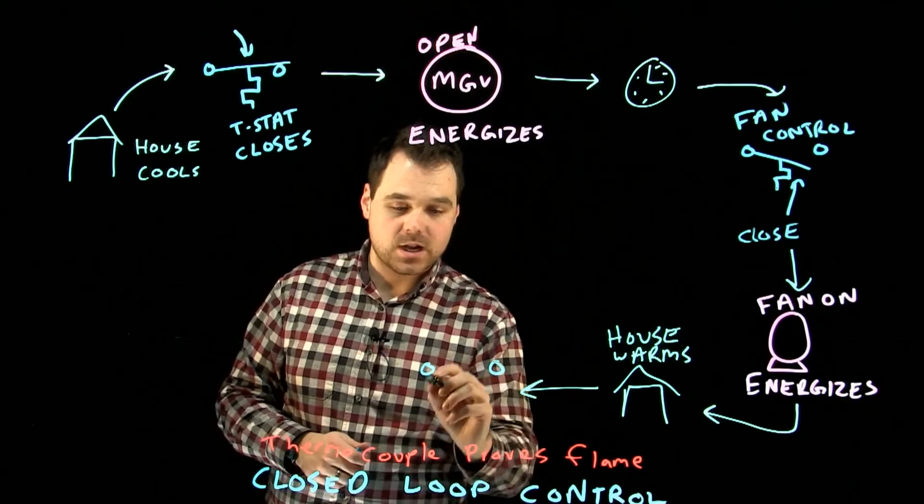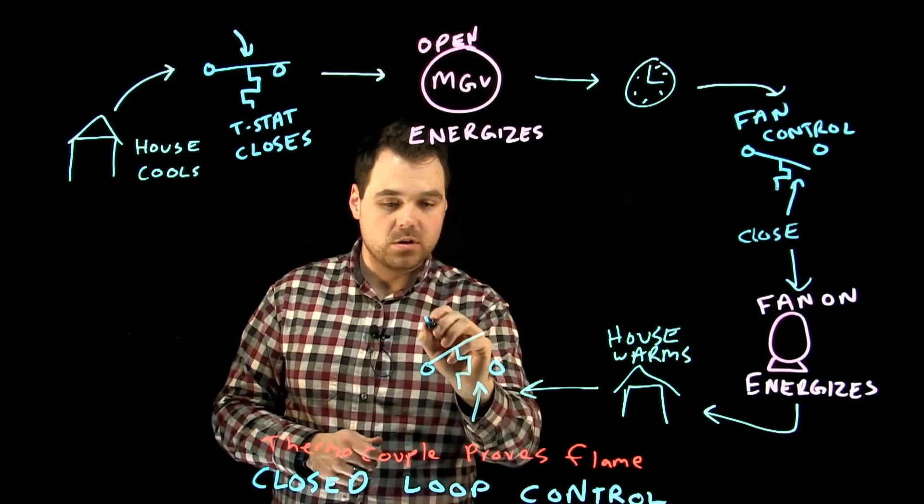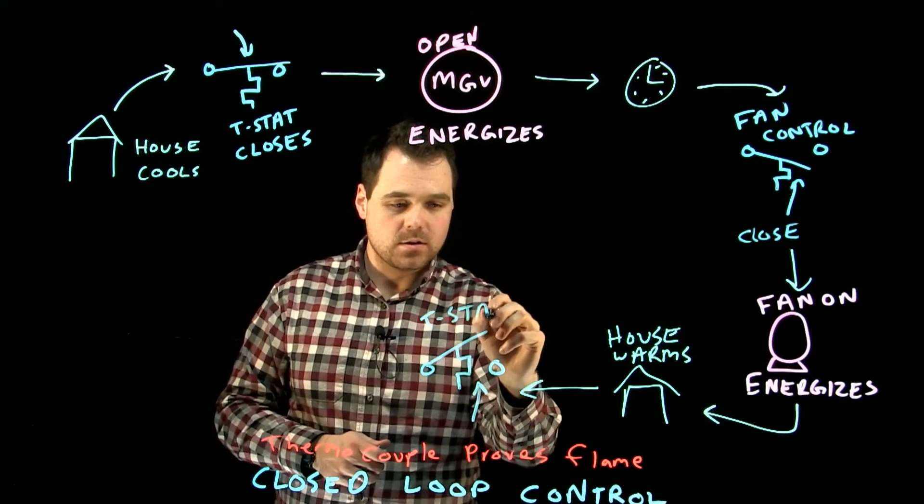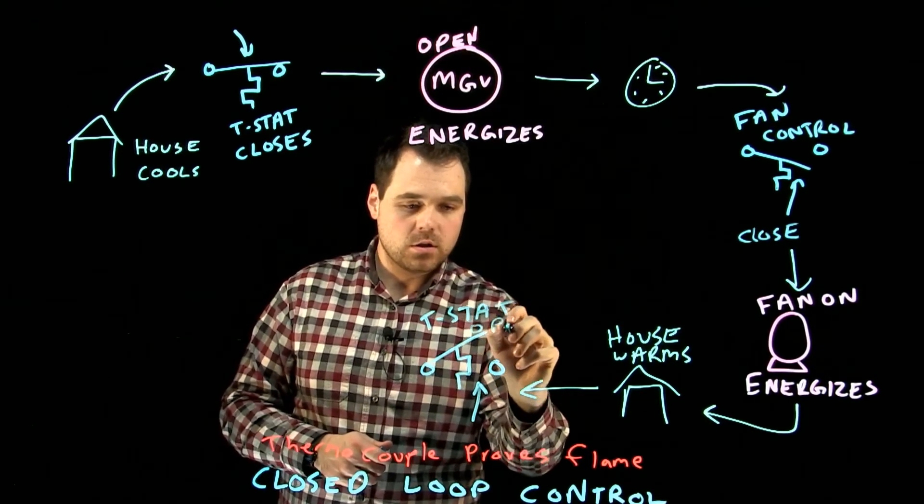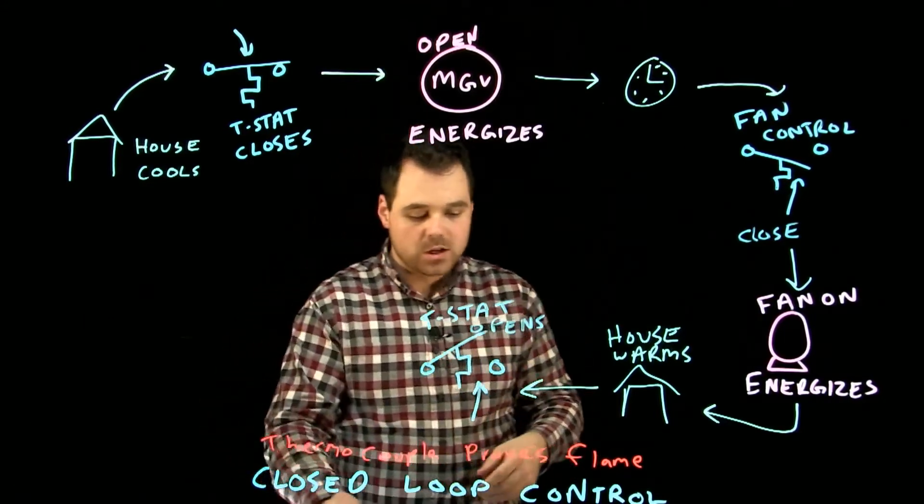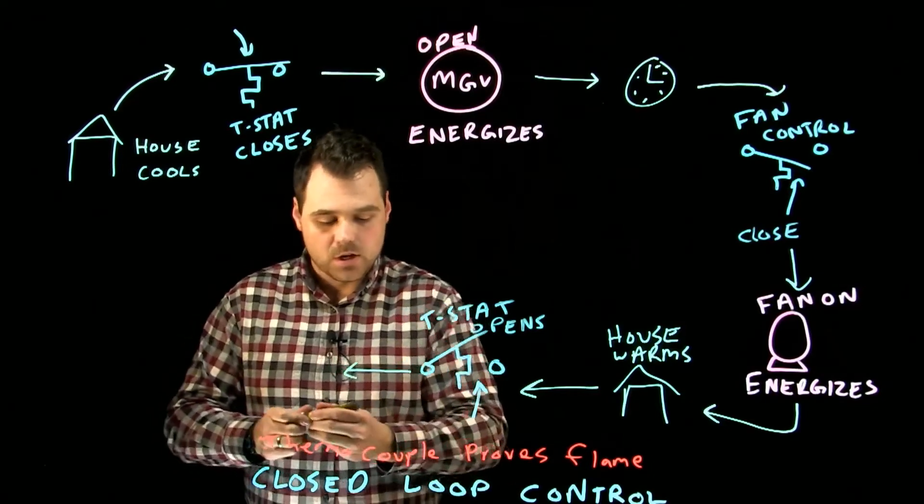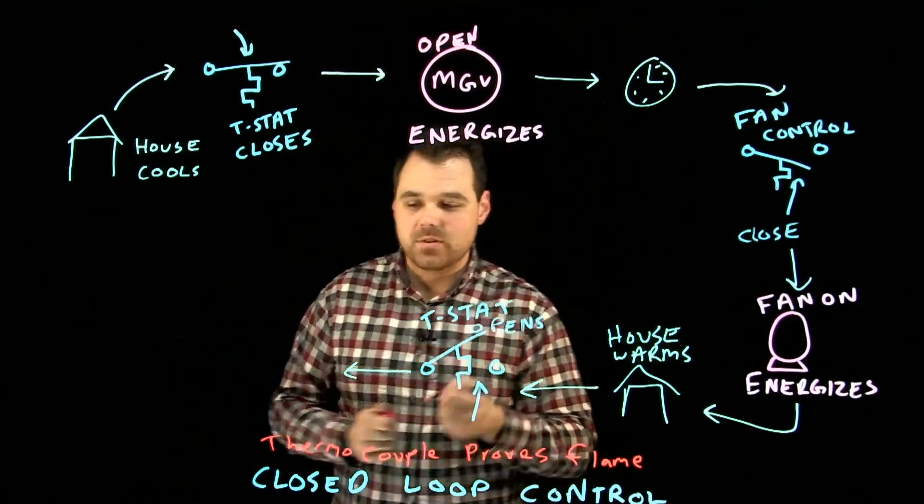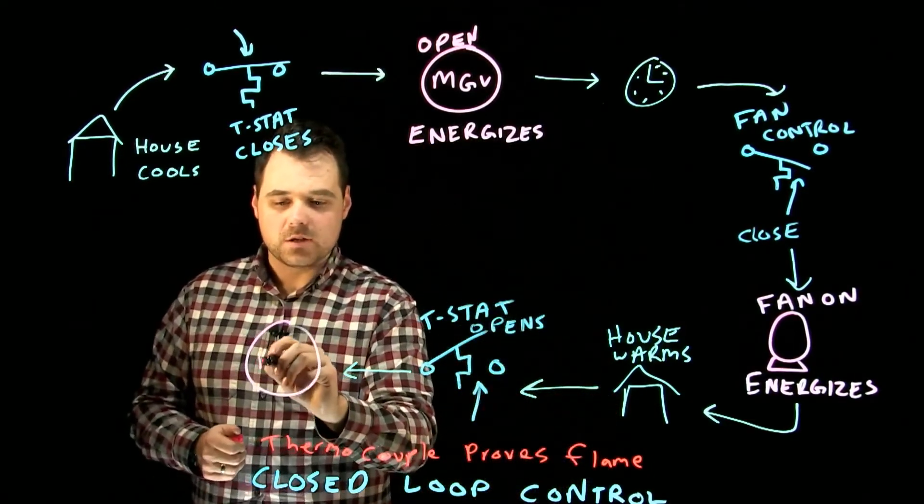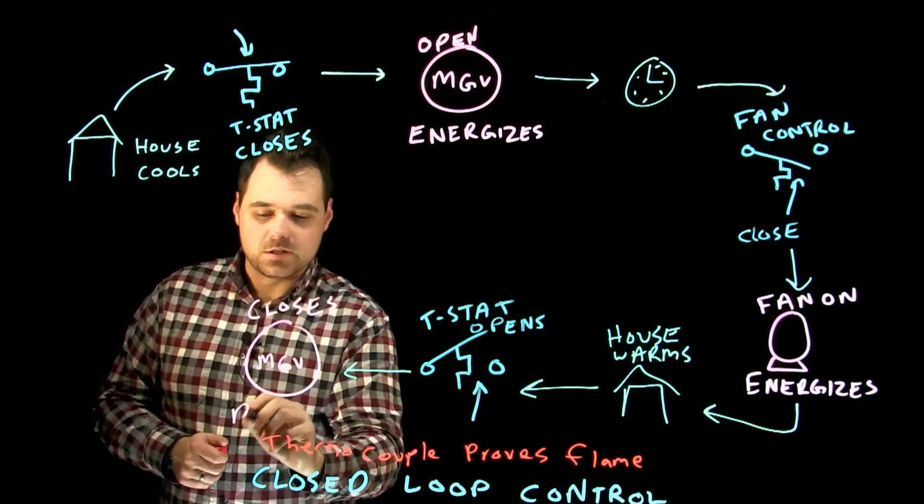Once the house gets warm enough, those thermostat contacts are going to open. The t-stat opens. As soon as the thermostat opens, it is connected directly in series with our main gas valve, so that main gas valve closes because it de-energizes.